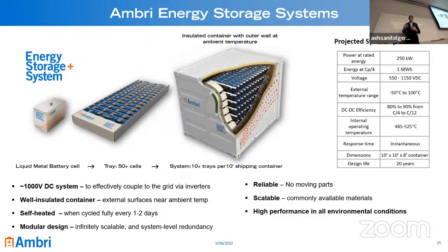We often get asked, don't we need to put a lot of energy into the battery to keep it hot? We do ship the systems cold, so we have electric heaters in the battery that we need to power when we first install the system. Once the system is up to operating temperature, as the battery charges and discharges it's not 100% efficient—it's 80 to 90% efficient. That loss, the 10 to 20% of capacity, is released internally as heat every time the battery operates, and that's all the heat we need to keep the system at its operating temperature.